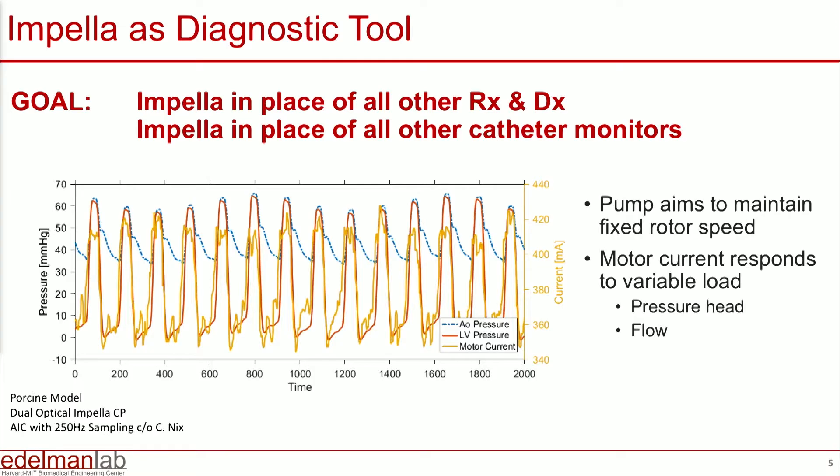In every single beat, in order to maintain that speed as constant, the Impella is sensing something in the ventricle and changing its current. What we and our colleagues reasoned was that we could use the amount of motor current being fed and the pressure head — because that's what you actually measure — and extract a variety of left ventricular metrics right from the indwelling device.